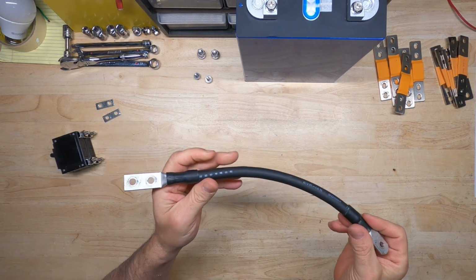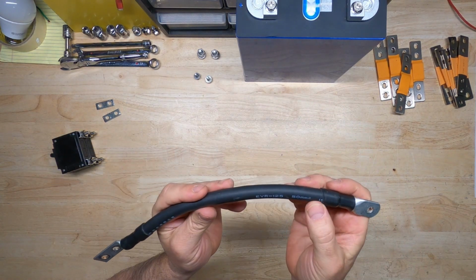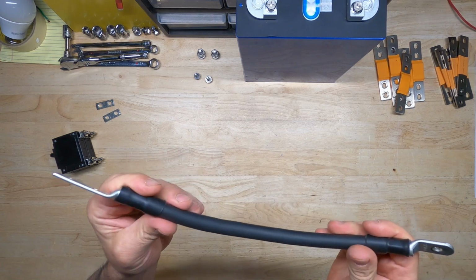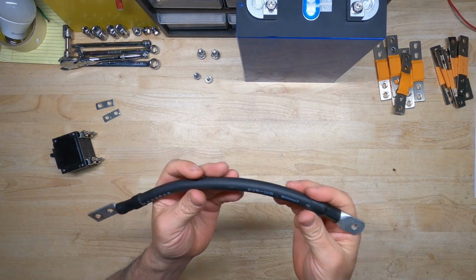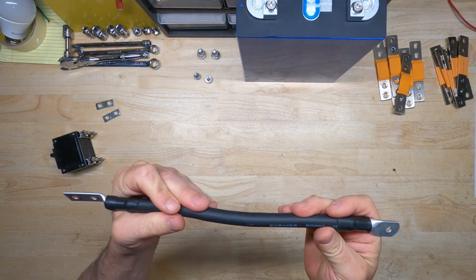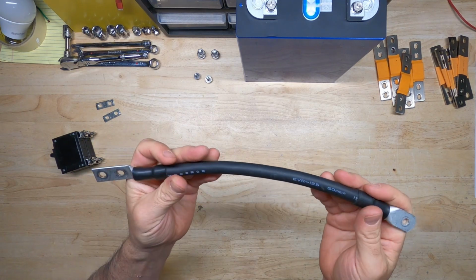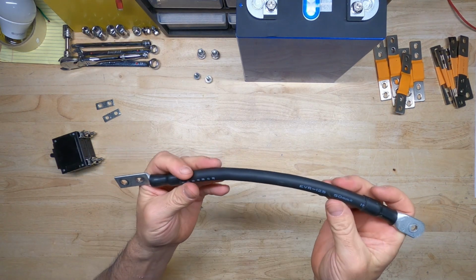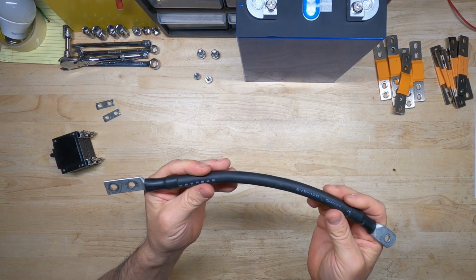And mostly that temperature came from the circuit breaker heating up the cable on the terminal and propagating the heat down the cable. As far as the cable itself, 50 millimeters squared, I think this is definitely sufficient for 200 amps. Sure, you can bring it up to 70. It's not much more expensive for these companies to do. There's no reason they shouldn't do it, really. But 50 definitely is sufficient for 200 amps.